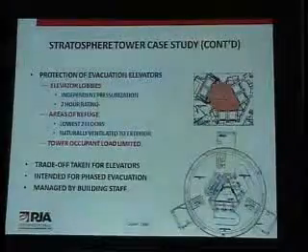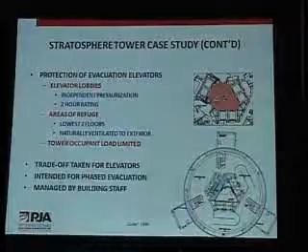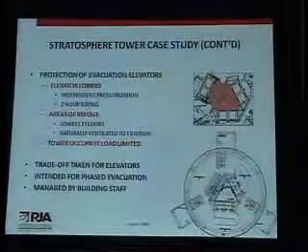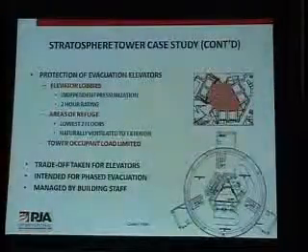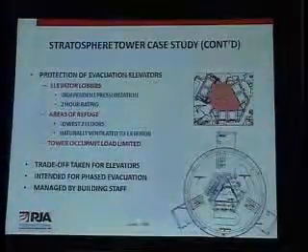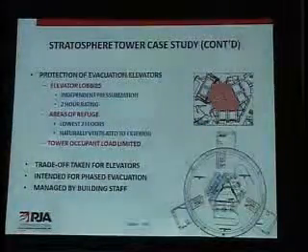So in this example, trade-offs were taken from elevators. But again, similar to Burj Dubai, the evacuation is intended to be managed. It's not a self-evacuation. Occupants come down to this floor. You can even see on the lower floor plan that there are already queuing lines established to queue occupants into these elevators.